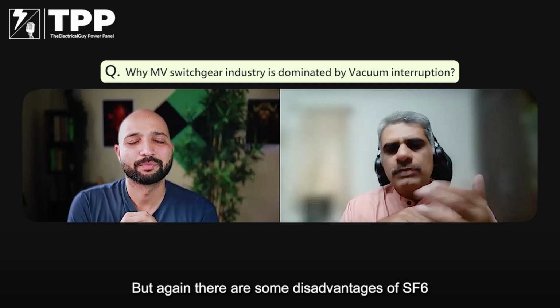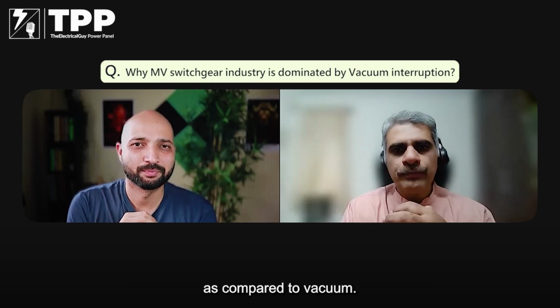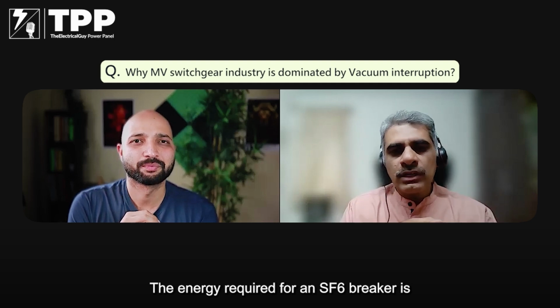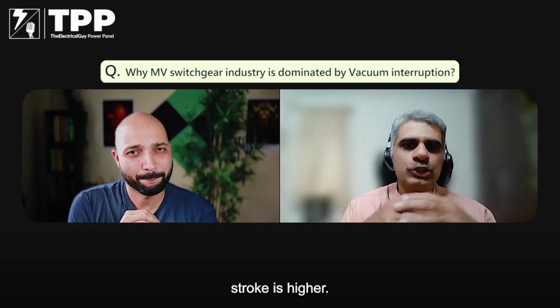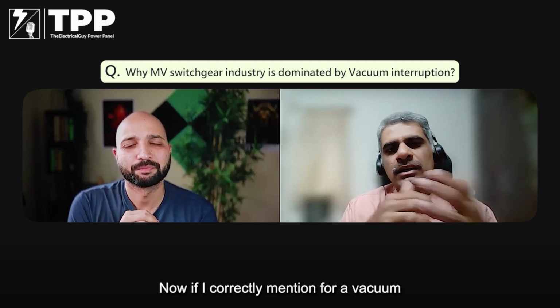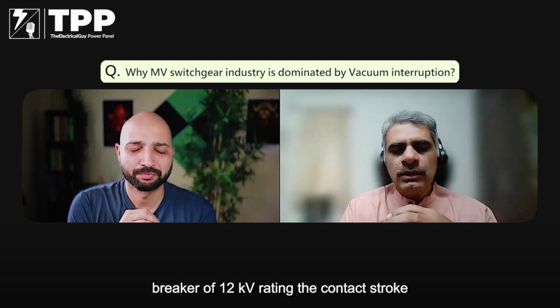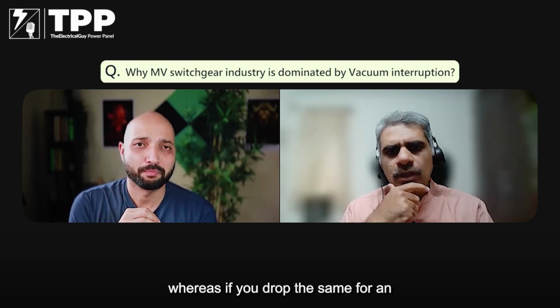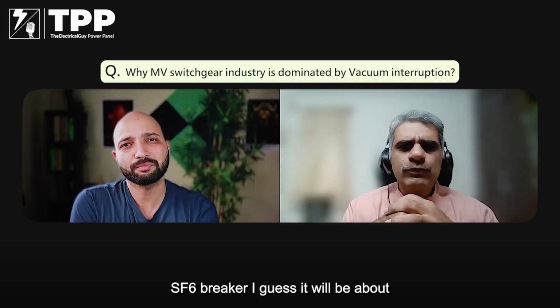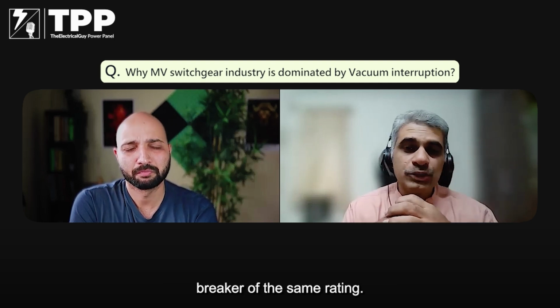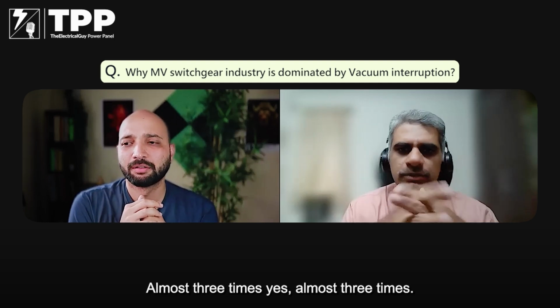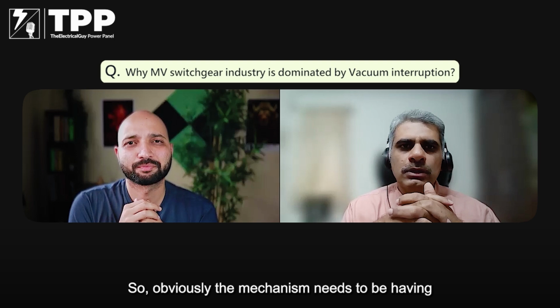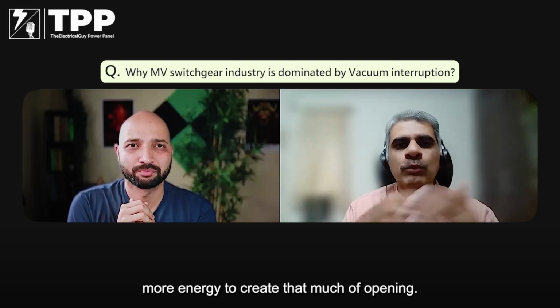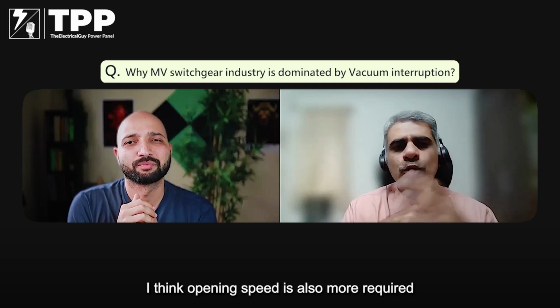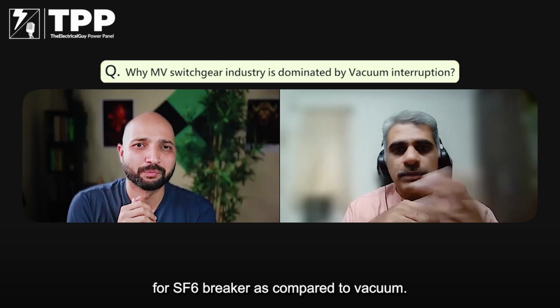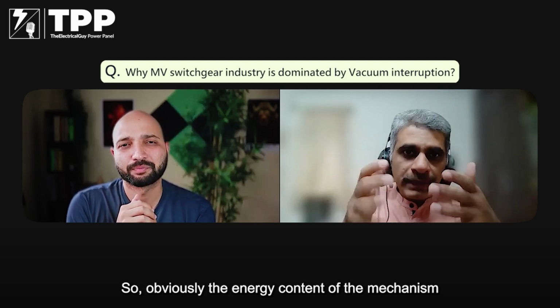But again, there are some disadvantages of SF6 as compared to vacuum. The energy required for an SF6 breaker is obviously higher than for a vacuum breaker because the stroke is higher. If I correctly remember, for a vacuum breaker of 12 kV rating, the contact stroke is not more than 6 to 8 mm. Whereas for an SF6 breaker of the same rating, I guess it will be about 30 mm. So almost three times, yes. So obviously the mechanism needs more energy to create that much opening. I think the opening speed required is also higher for SF6 breakers as compared to vacuum. So obviously, the energy content of the mechanism is higher.